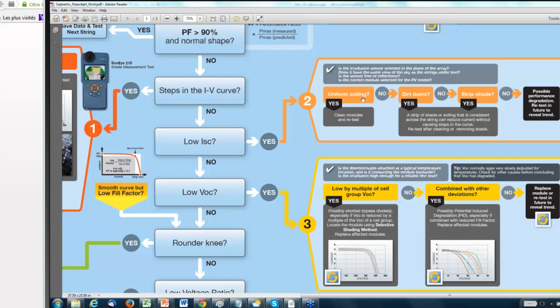If you go all the way to the right in block number 2 and still haven't found a reason for it, it's possible you have performance degradation in the short circuit current. You'd want to make a note to revisit this string in the future to test it and see if there's a continuing trend.